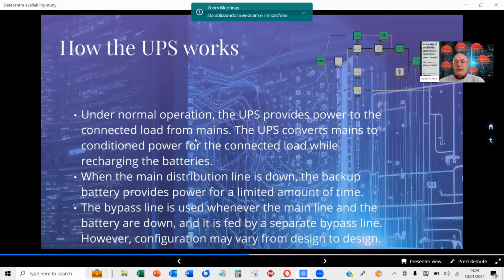Under normal operation, the UPS provides power to the connected load from the mains, and converts the conditioned power to the connected load while recharging the battery. So it does two things: first, it makes sure you've got a very smooth supply, and at the same time it recharges the battery in case things go wrong.